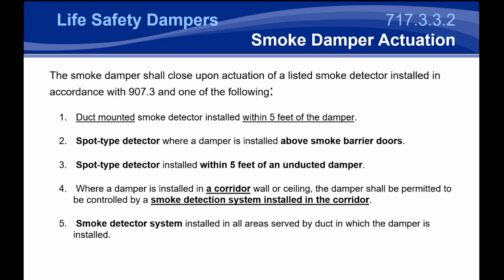And typically when you're dealing with tenant improvement, there's not a lot of clearance to be able to install a damper to bring a building up to a newer version of building code. Because of that, I typically recommend having the smoke detectors mounted loose. There's a couple of benefits to that.